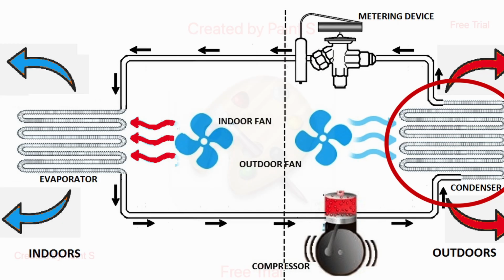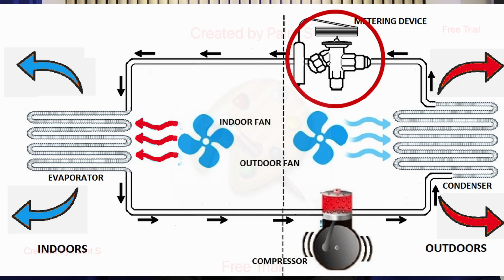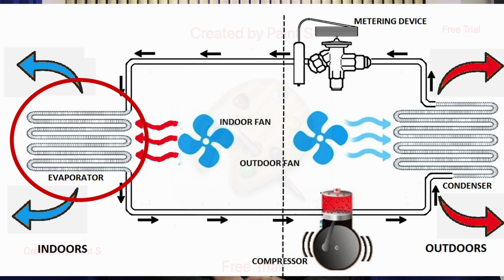Moving on from the compressor, the refrigerant enters the condenser, which is the part with a big fan in the outdoor unit. Here, a part of its temperature is taken away, but the pressure stays almost the same. Therefore, the refrigerant is now no longer in balance. It has the pressure, but it doesn't have the temperature. It's eager to get back the energy lost. The refrigerant is then forced into an expansion valve that drops its pressure. And when the opportunity presents itself in the form of a nice evaporator, that energy is quickly drawn from the air back into the refrigerant, from the indoor air.